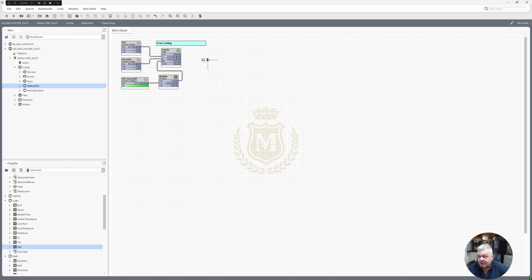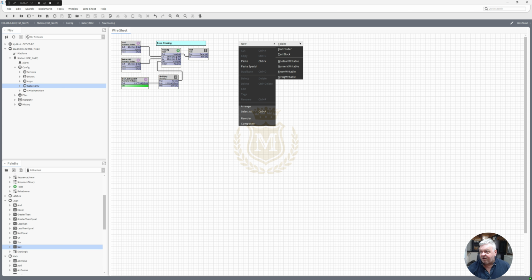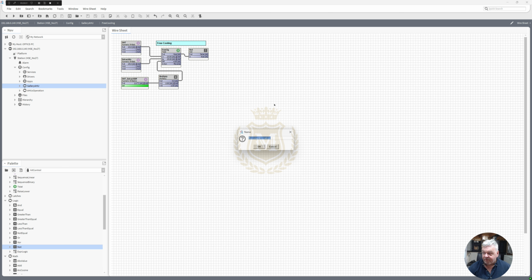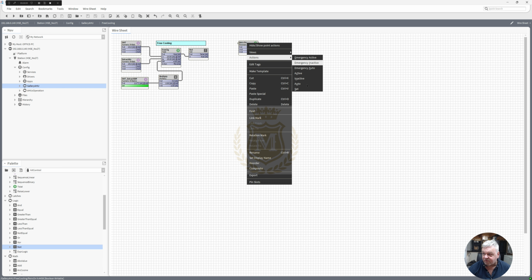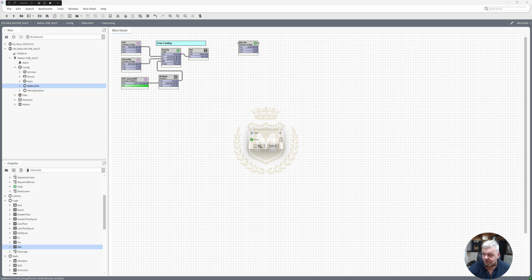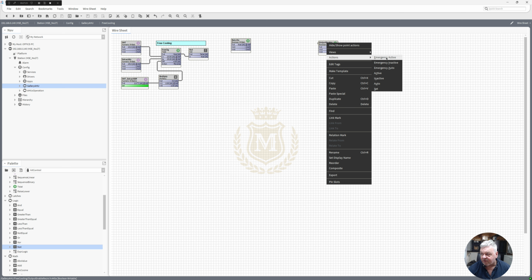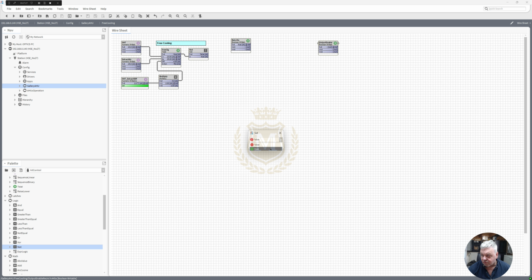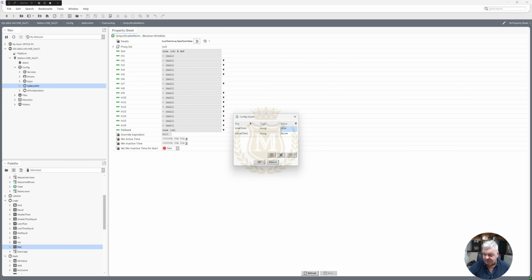Logic NOT. So if you've got your logic that is recircing at the moment, so say we've got recirc on, new boolean writable, so recirc on, so we're recircing on at the moment, action set to true. So in the logic somewhere the recirc is on, and new, and the boolean writable output, enable recirc. If it's just an on and an off, actions set that to true, enable. In fact, let's just change the text there and just put it to enable and disable.